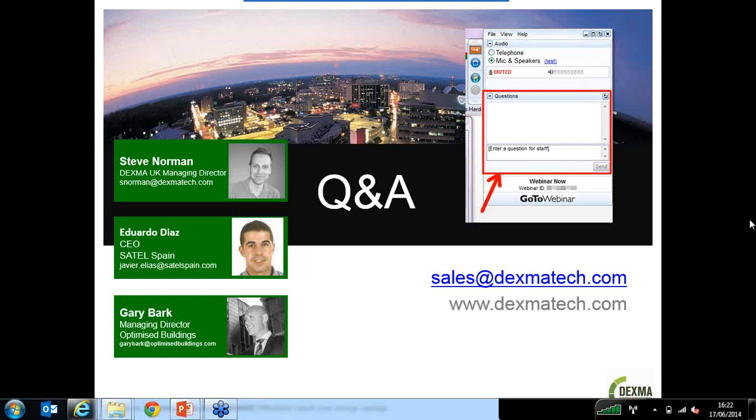It's actually not a gas CHP. It's a bio oil CHP. So they have deliveries of oil in big tankers every couple of weeks. It's not a cheap oil, I think generally in the order of 75 to 80 pence per litre. But it's a complete waste product, which means that in the UK they get something called Renewable Obligation Certificates, the ROCs, and it's those ROCs that make paying that sort of price for oil viable. The renewable element gets traded through the ROC certificate, which brings the CHP, the maintenance, the oil, and the delivery of that power down to about 8.5 pence per kilowatt.